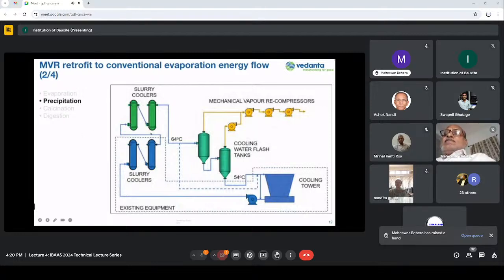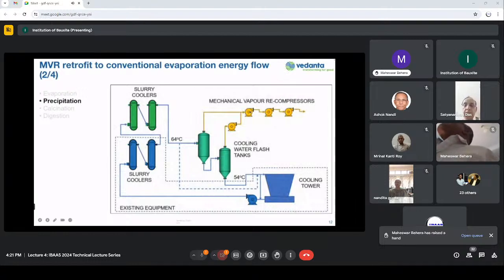And also in this case, as we see here, like the evaporation, the vapor from the last flash tank goes to the first stage compressor, where the pressure raise needed, the difference between the pressure requirement, is higher, and the tank just before that goes to the second MVR. So this way we can flex or adjust, depending on the steam requirement, how much MVR to use, and the steam consumption can be optimized.